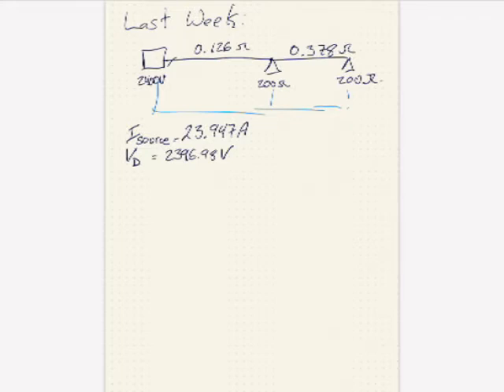So we took a look at our example from last week and we saw that we were sitting at about 24 amps. That's quite lightly loaded. As a result, when you get out to the end of our circuit, this customer has almost no voltage drop at all across the length of the line. So he's still getting really nice quality power delivered to the premise. So things are good. Now, this week, let's take a look at what happens when things go bad.